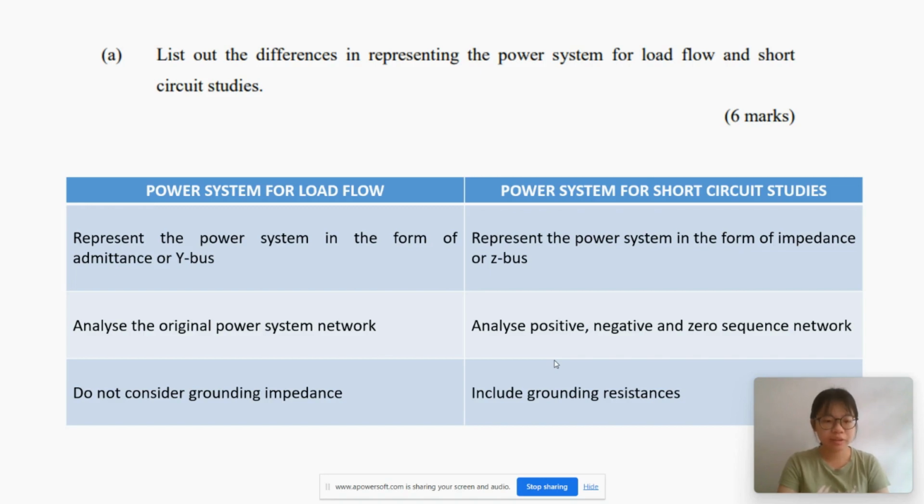The last difference is we do not consider the grounding impedance in the load flow studies, but we include the grounding resistance in the short circuit studies.